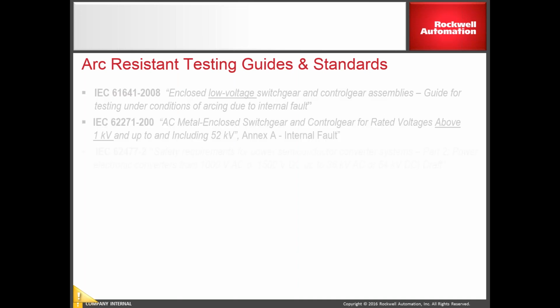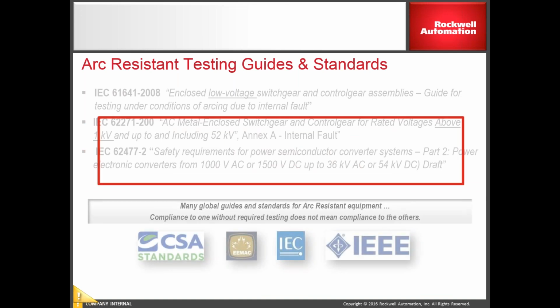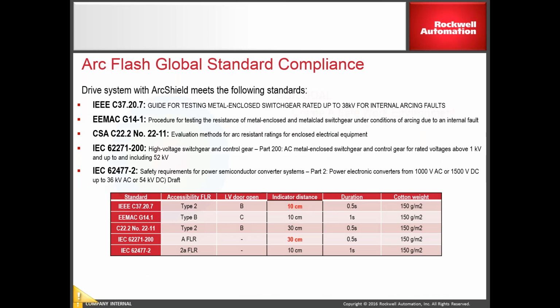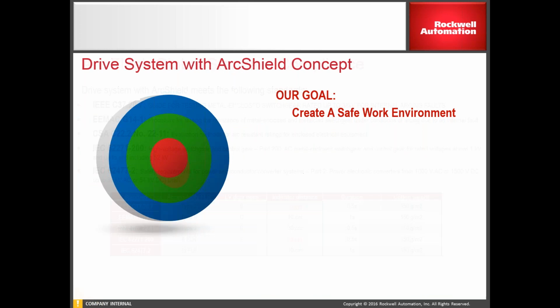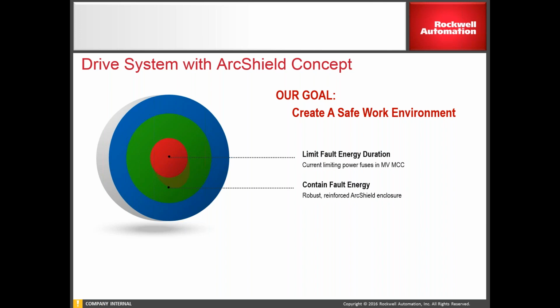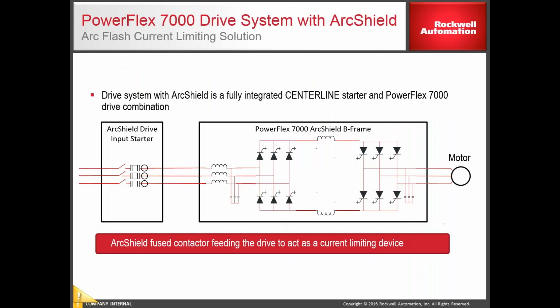So again, a little bit more on the standards. Again, we meet all these standards. We have documentation that we can provide if it's required, but that's the list of global standards that we're compliant with. So again, the idea is to create a safe work environment, right? We can limit the fault energy duration using the current limiting power fuses. We can contain the fault by beefing up the structure to make sure no doors fly open in the event of a fault. And then we can also redirect it with the chimneys or the plenums that we use to direct the energy outside of the enclosure.